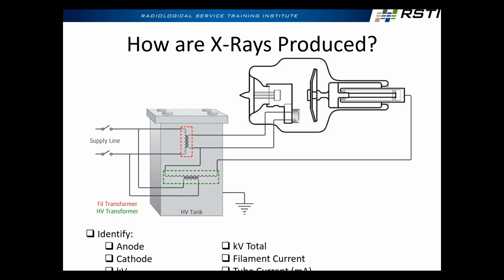The higher I go in kV, the faster those electrons are moving across that tube, or a more accurate way to put it is the more kinetic energy they have, all right? It's that kinetic energy that's going to get converted into heat and X-ray photons. About what percentage of that do you think is going to be X-rays? Yeah, maybe 1, right? So when I said we didn't have a very efficient system, that's what I was talking about. Over 99% of the energy that we put into this X-ray tube gets converted into nothing but heat.